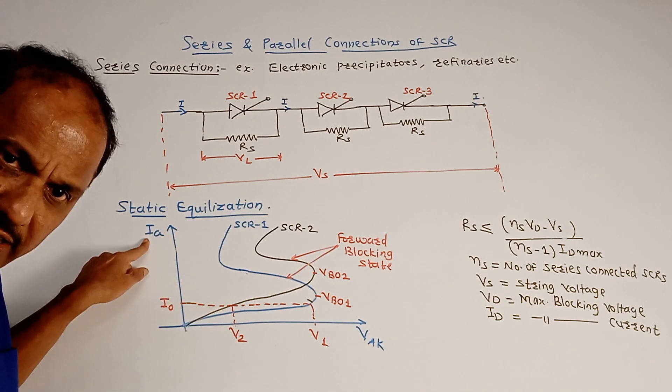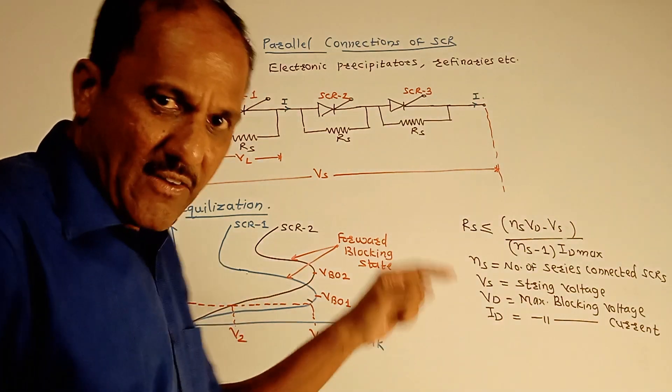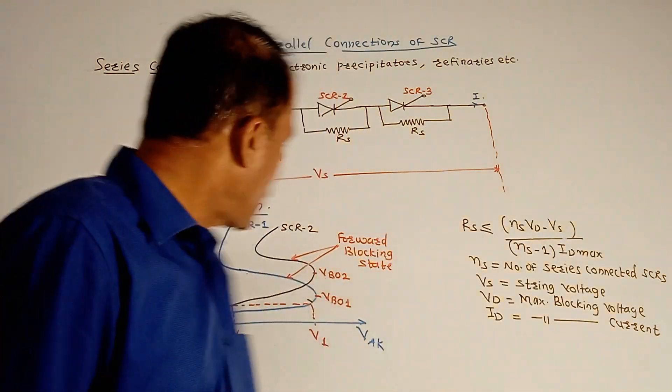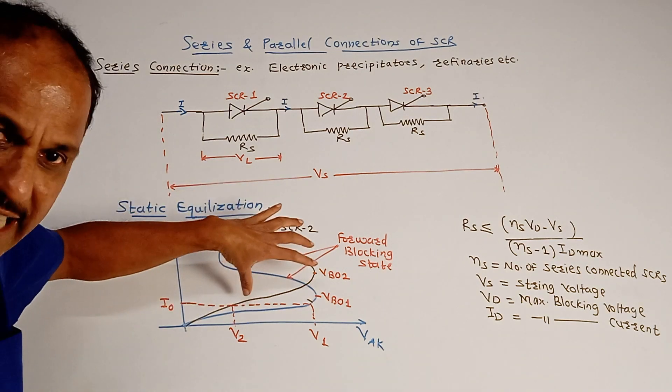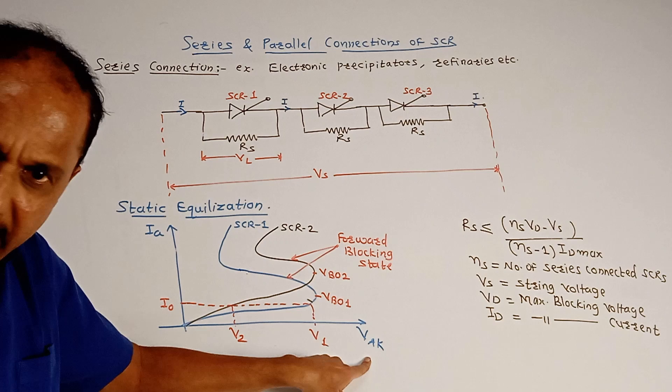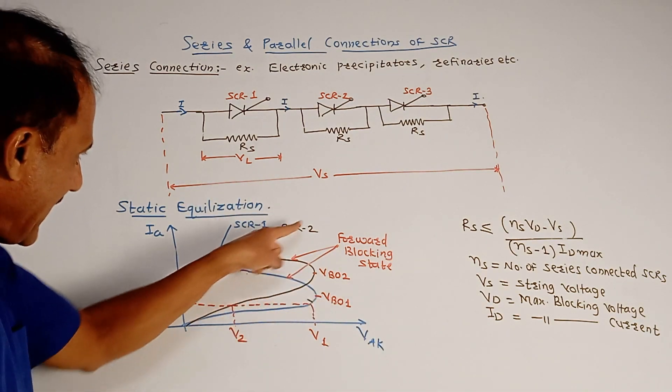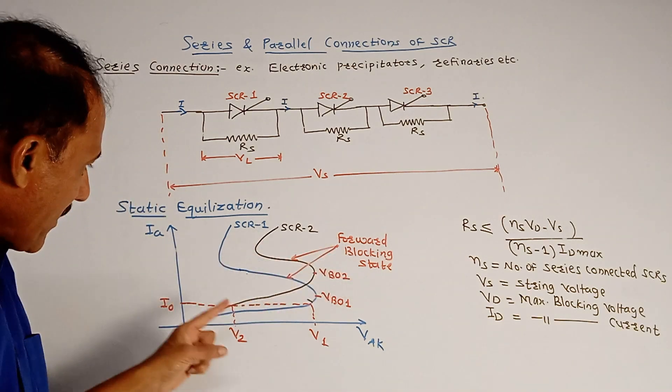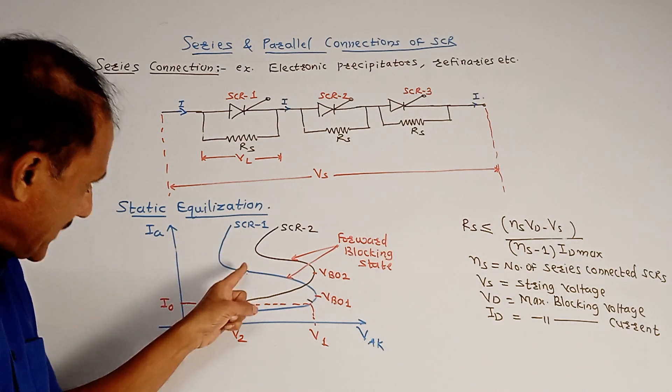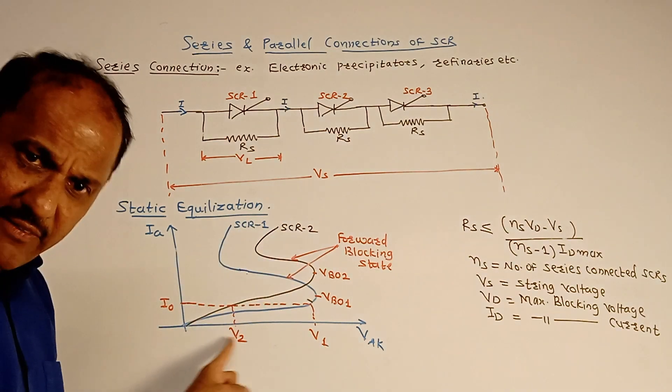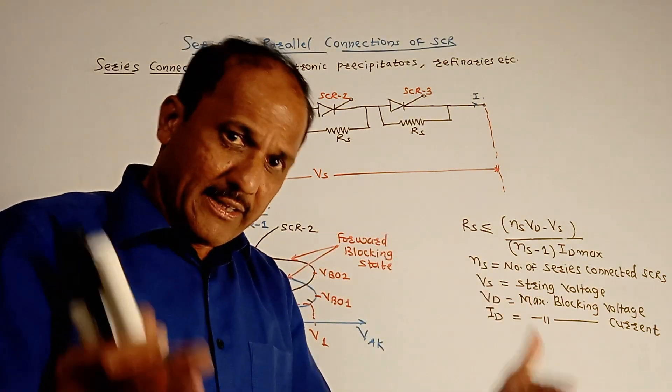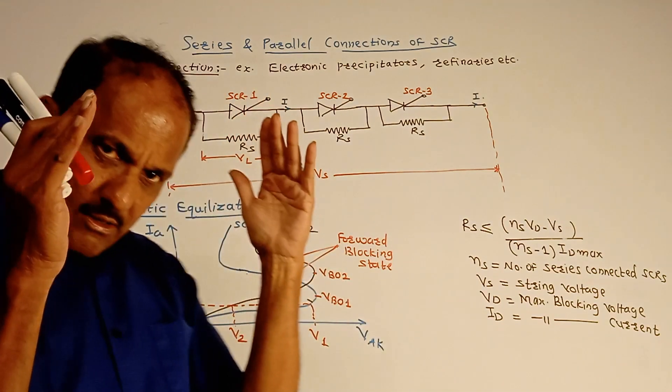Consider a graph, this is the graph of anode current IA versus VAK. VAK is voltage between anode and cathode. So there are inherent or internal variations of anode current versus VAK which is shown in this diagram. I have considered two SCRs, SCR1 and SCR2. Now consider certain leakage current I0. But for the same level of I0, both SCR voltages, that is for SCR1 and SCR2, voltages are V1 and V2. These voltages are different, these voltages are not same. That means whenever the SCRs are in off state, due to certain inherent variations, the voltage rating related to each SCR will be different.